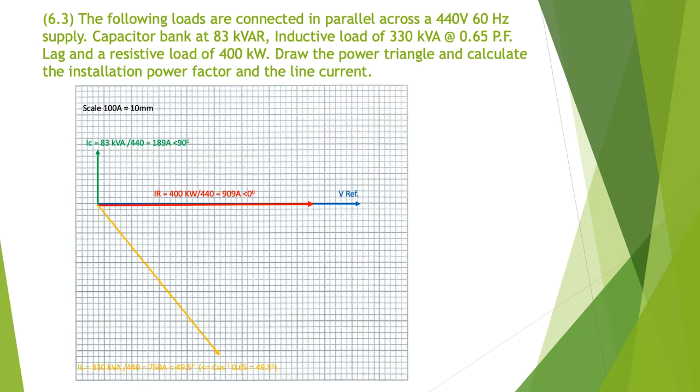And then finally we've got our orange one which is our inductive load of 330 kVA at 0.65 which is about 50 degrees. So we've put that in. So I worked it out down here, you can see cos to the minus one of 0.65 I've turned that back into an angle. So that angle in there is our 49.5 degrees. The length of each of the lines representing the current, so we use that and we end up here with a current of 750 amps.